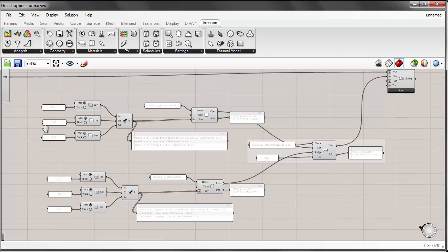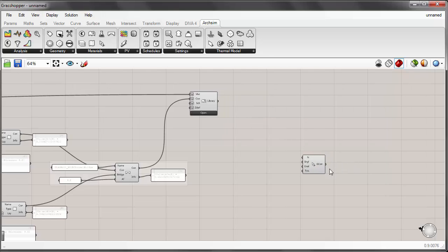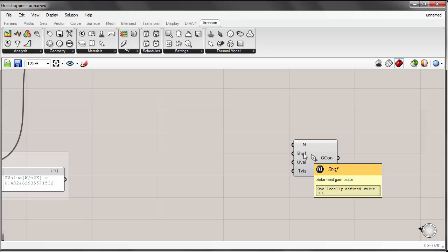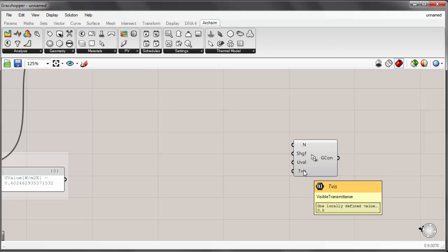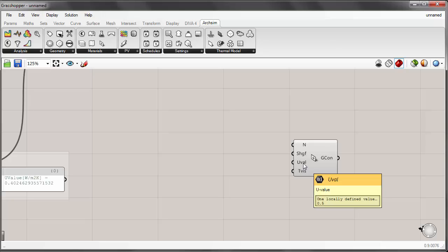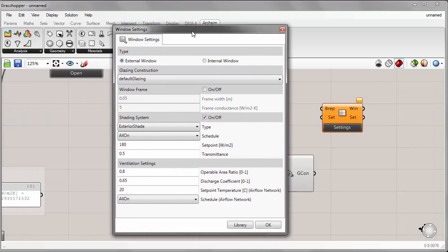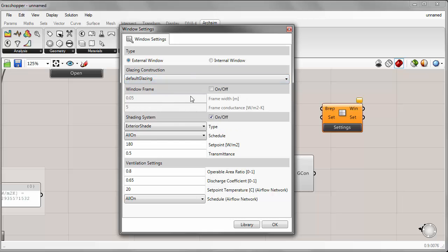Now that we've done custom opaque materials and a construction assembly with a thermal bridge, let's look at how to create custom glazings. I'll place the simple window component onto the canvas. The simple glazing component works using three primary inputs: the solar heat gain coefficient, the overall U-value of the glazing assembly, and the visible light transmittance. It's important to keep in mind that the U-value is for whatever glazing material you're prescribing, and it's up to the user whether this considers the frame or just the glass.